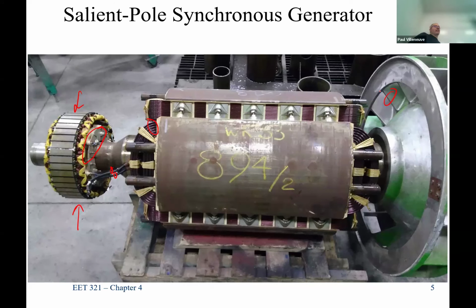They never look this clean unless it's being rebuilt. This is still in the shop, you can see it's going to be put in the shaft, but it's wound already. You can see the purpley windings, remember that's not purple copper, that's just the insulation on the wires. I wonder if I can zoom in a little bit. I can't, but you can see the size of the conductor, so fairly decent sized conductors. And then they're spaced and kept together with something like a paper tape, they just tape it around to keep it in position.